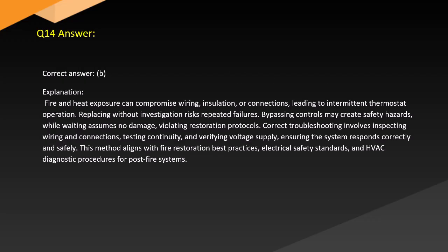Answer. Correct answer. B. Explanation. Fire and heat exposure can compromise wiring, insulation, or connections, leading to intermittent thermostat operation. Replacing without investigation risks repeated failures. Bypassing controls may create safety hazards, while waiting assumes no damage, violating restoration protocols. Correct troubleshooting involves inspecting wiring and connections, testing continuity, and verifying voltage supply, ensuring the system responds correctly and safely. This method aligns with fire restoration best practices, electrical safety standards, and HVAC diagnostic procedures for post-fire systems.